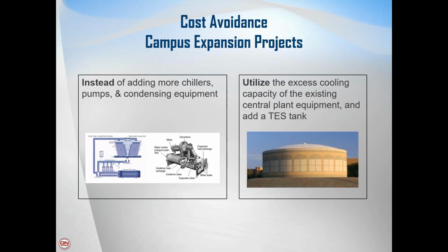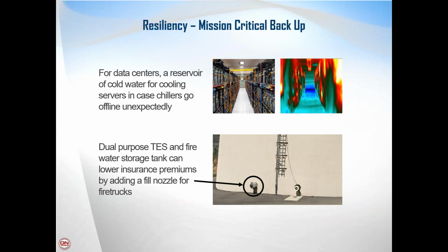And that tank has no moving parts. It has no horsepower pumps driving refrigerant. It is just a tank, a reservoir to hold cold water. So there's very little maintenance, if any, with a tank compared to the refrigeration equipment on the left. So there's a significant operation and maintenance reduction when you compare a tank to adding more chillers or cooling towers to a system.